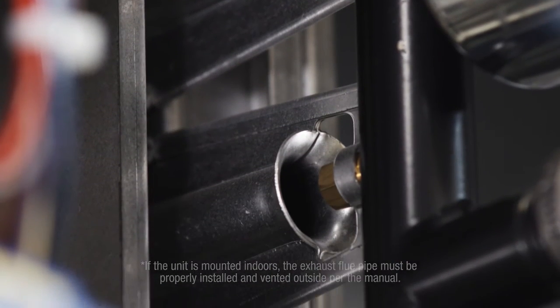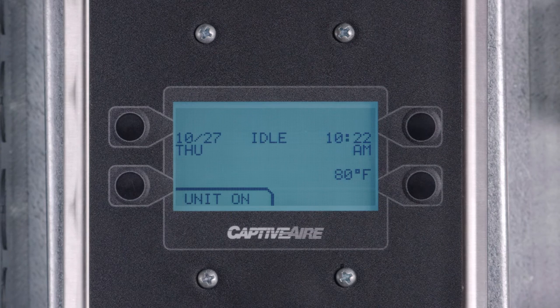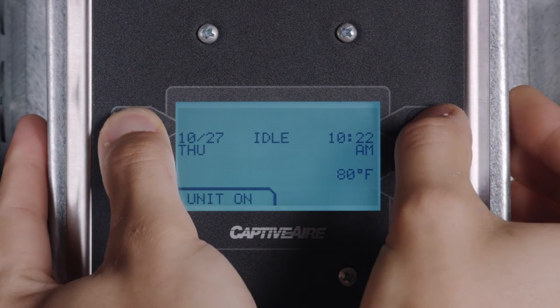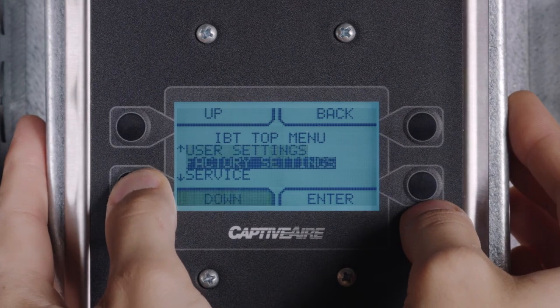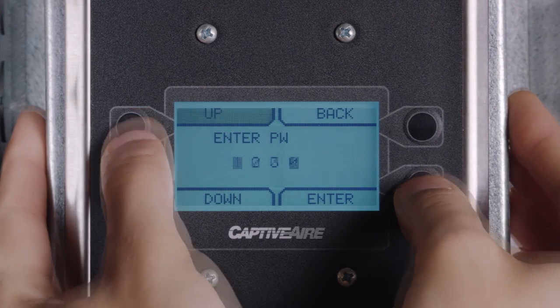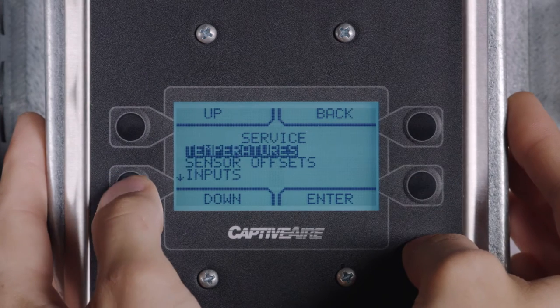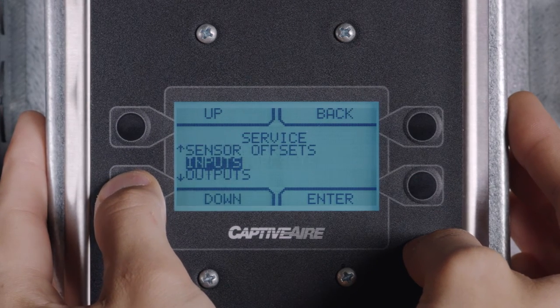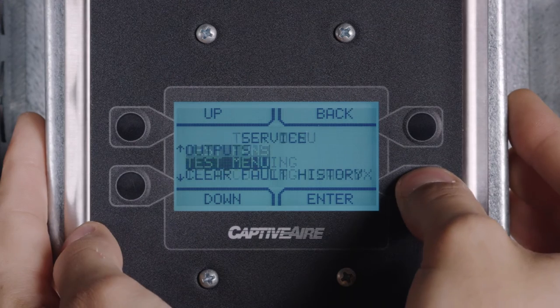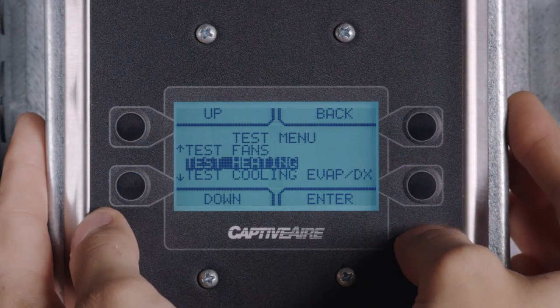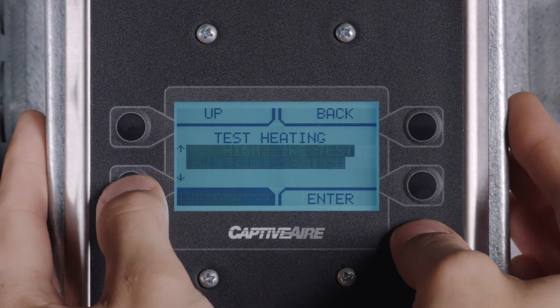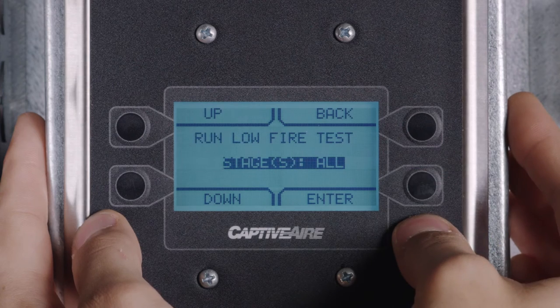Next, the low fire gas pressure needs to be adjusted. To do so, first access the menu, then select service, enter the password 1234, select test menu, test heating, run low fire test, all stages.